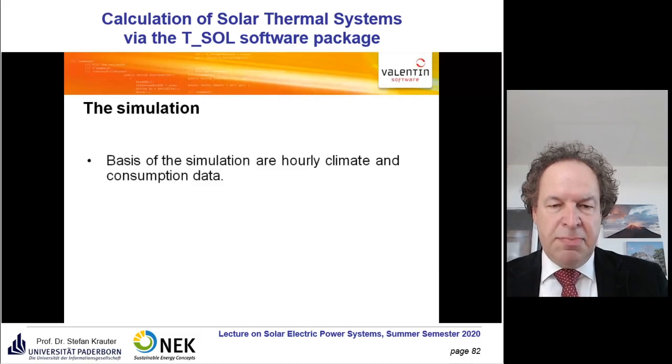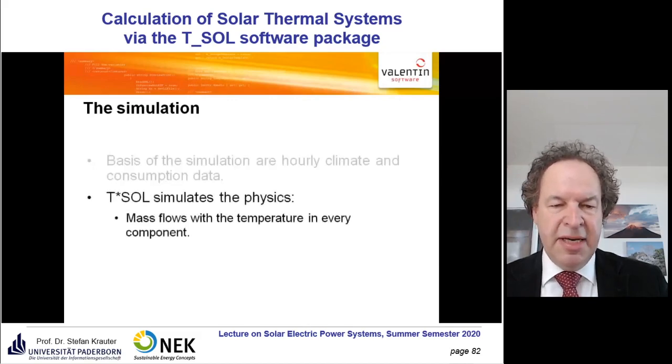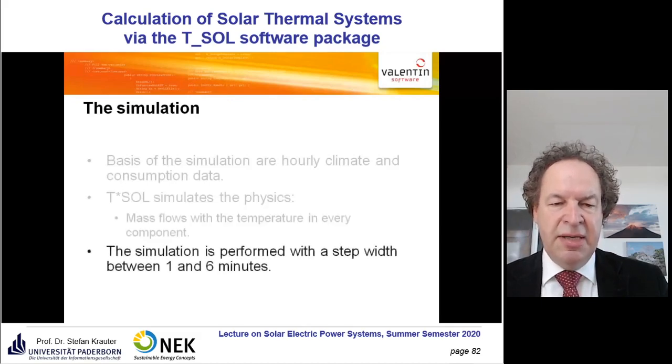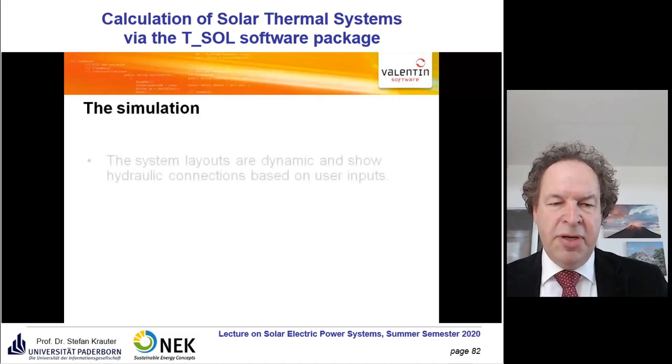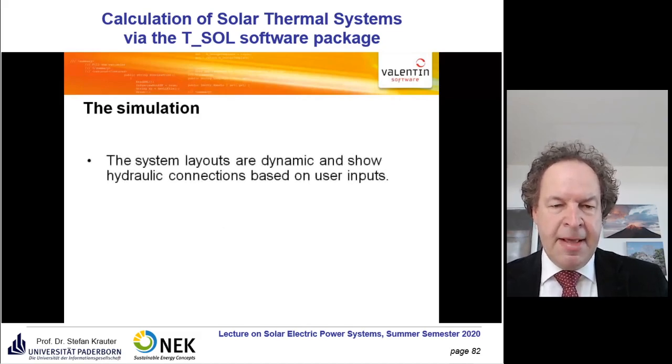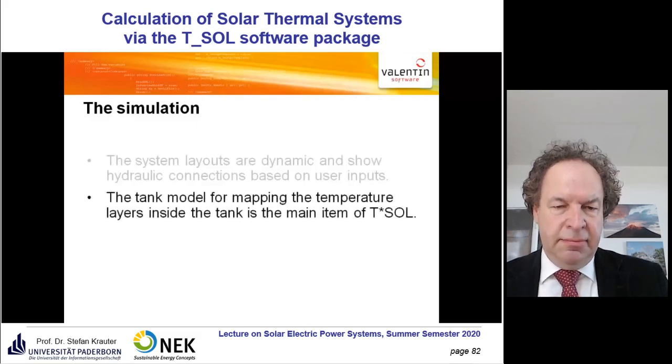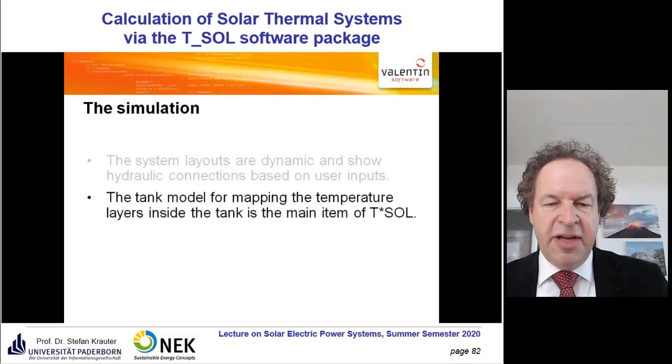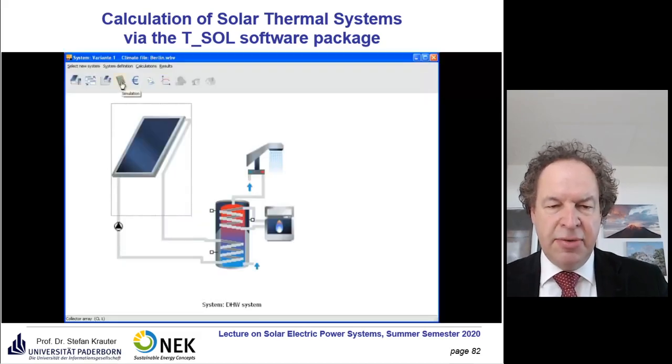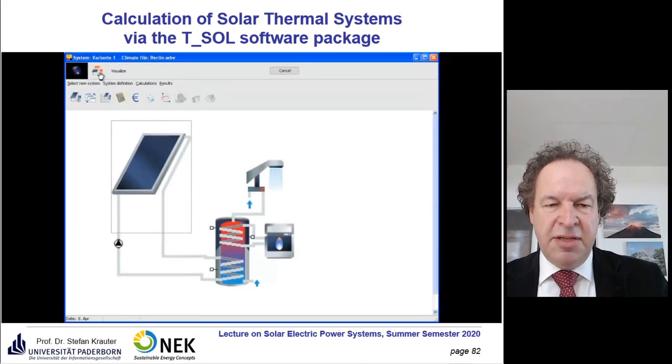So it's just based on hourly climate data. Better if you have half an hour or minute data, and then it calculates the mass flows within every component and performs a step within 1 to 6 minutes. Yes, we have the tank layers, so the stratification inside the tank is also calculated. So you can start a simulation now.